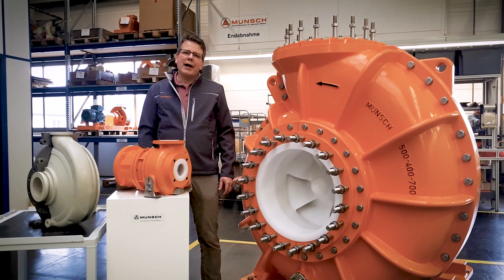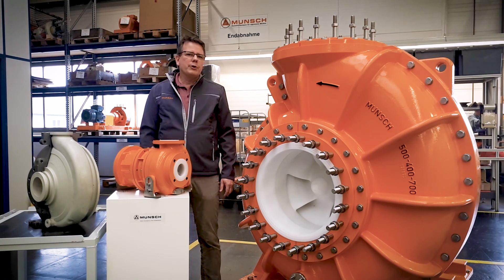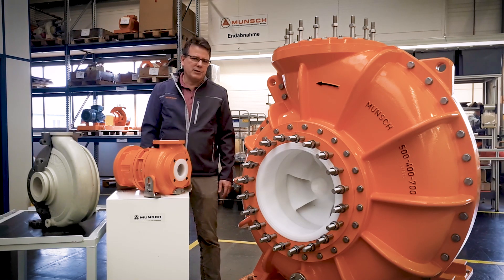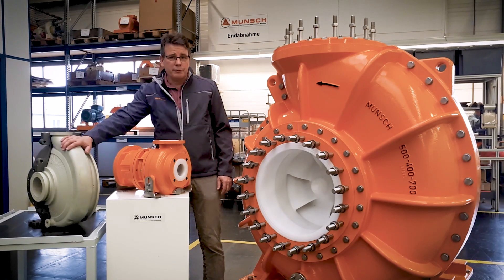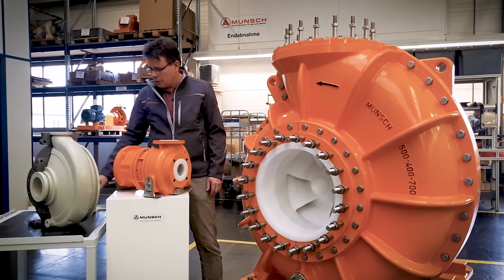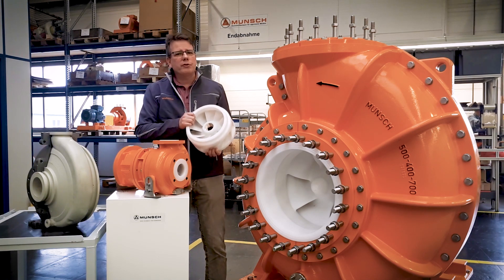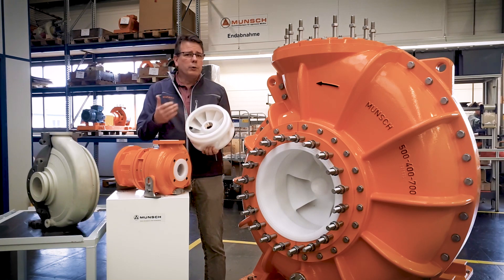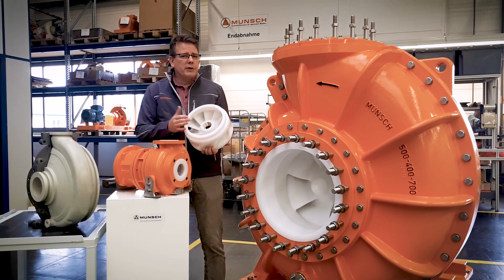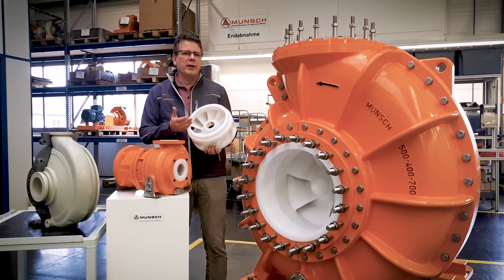Munsch does not make linings in their pumps. All of the pumps that we do here are from solid plastic. You can see this with the pump casing we have here with several centimeters of wall thickness, and also with the impellers that we have. This is the key to success when it comes to challenging media that not only contains slurries but sometimes even have compounds that are able to permeate through the plastic.